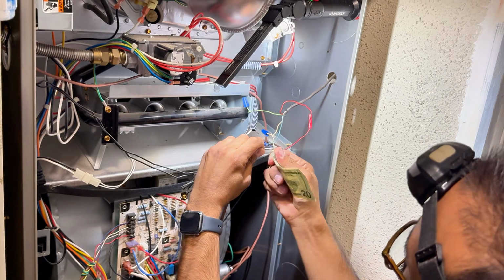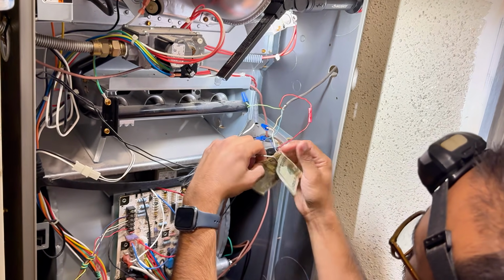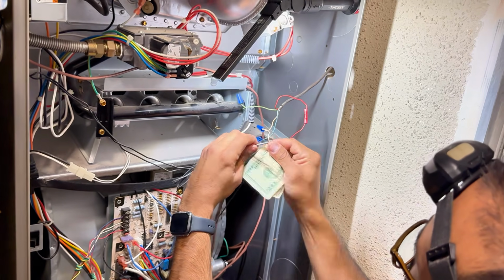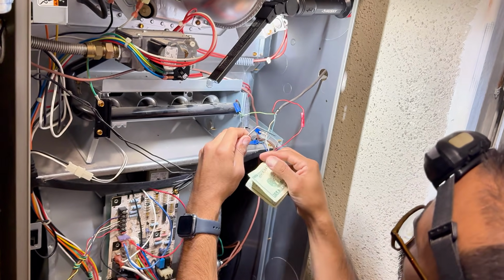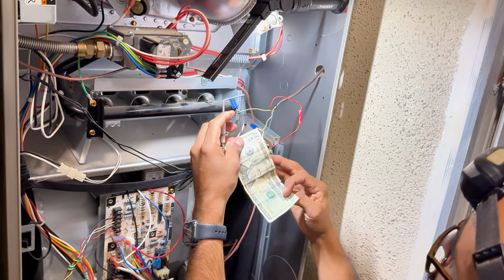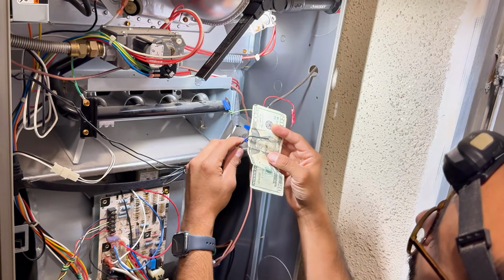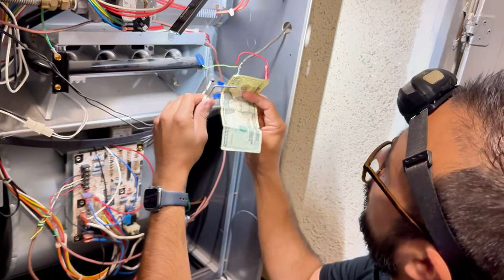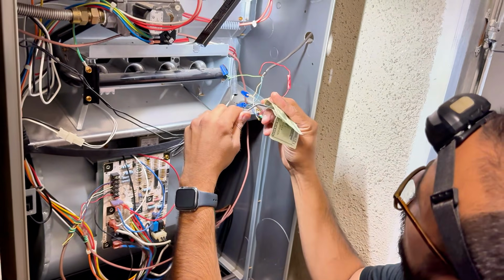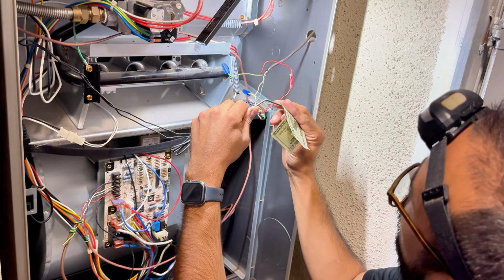I'll show you how to check the flame sensor with the meter too, to make sure it's working. Some flame sensors, even if you clean them, you just have to replace at some point, but all I'm doing here is cleaning it.